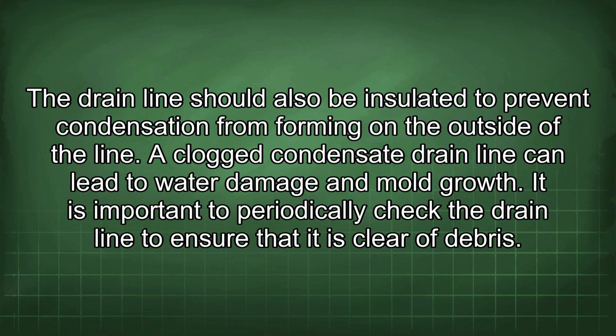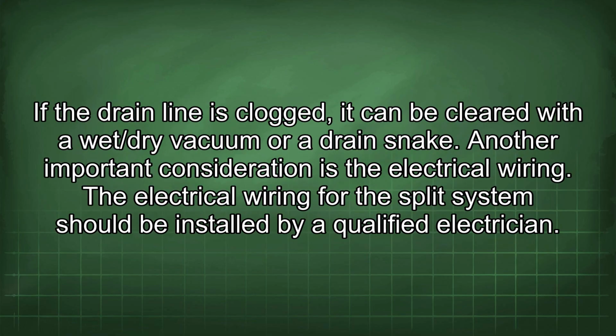A clogged condensate drain line can lead to water damage and mold growth. It is important to periodically check the drain line to ensure that it is clear of debris. If the drain line is clogged, it can be cleared with a wet/dry vacuum or a drain snake.